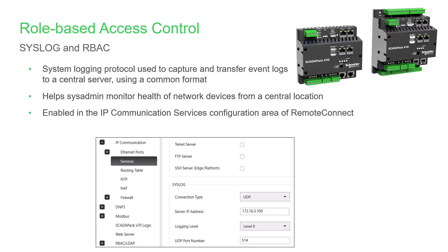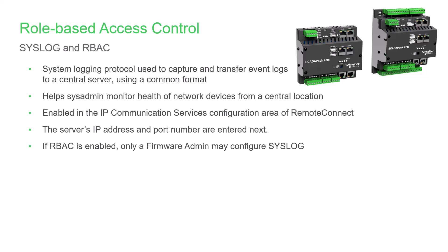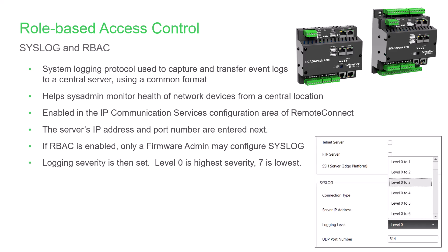Enable Syslog in Remote Connect by going to IP Communication on the Configuration tab and selecting the Services option. The connection type is always UDP. Configure the IP address and UDP port number. When role-based access control is enabled, only a user logged in with the Firmware Administrator role may configure Syslog. Then the logging severity level is selected.